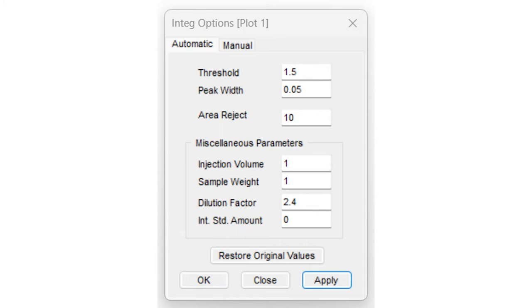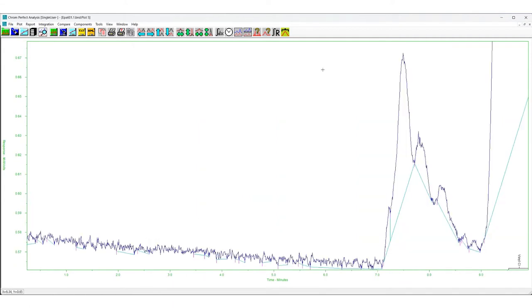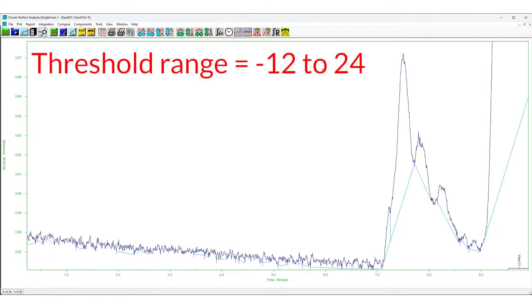The proper value for the threshold is determined by the amount of noise on the chromatogram trace. Because noise varies over a wide range, the threshold is a logarithmic quantity, specified as a dimensionless number in the range minus 12 to plus 24. Fractional values are legal, but rarely necessary. A threshold of zero corresponds to a minimum peak area of about 50 microvolt seconds, and the minimum value doubles every time the threshold is incremented by one.